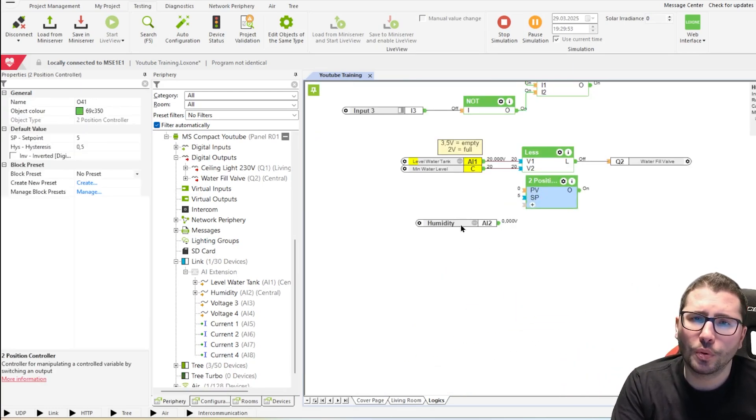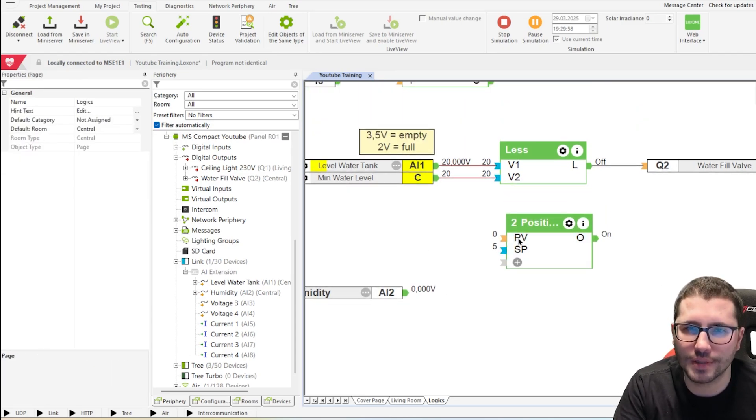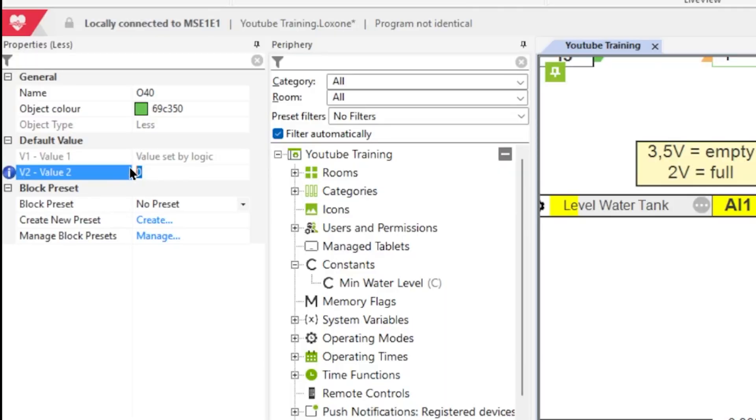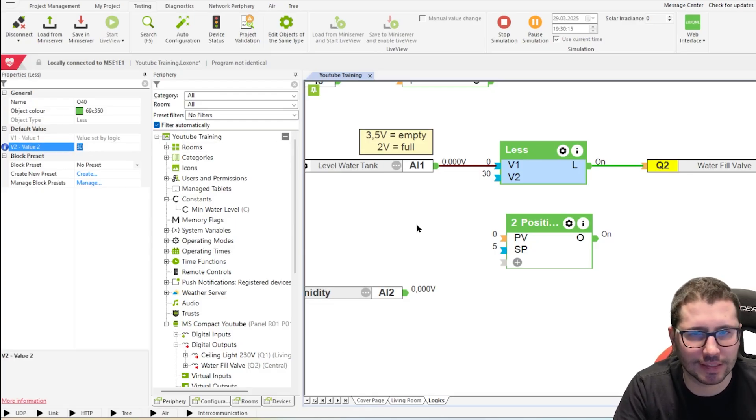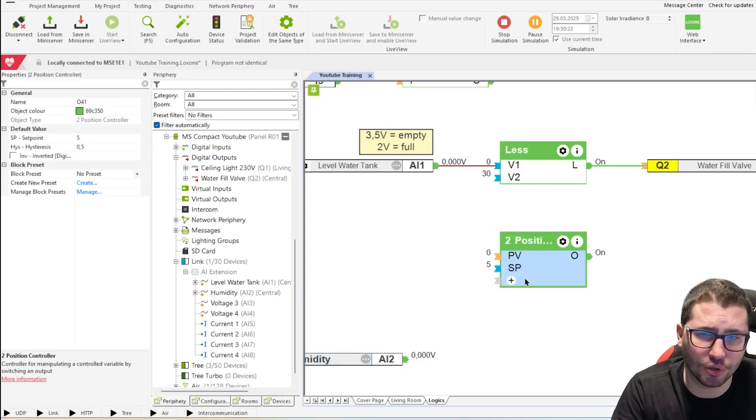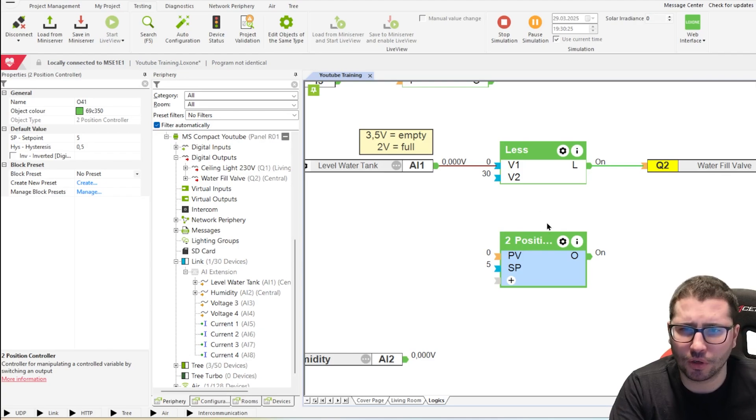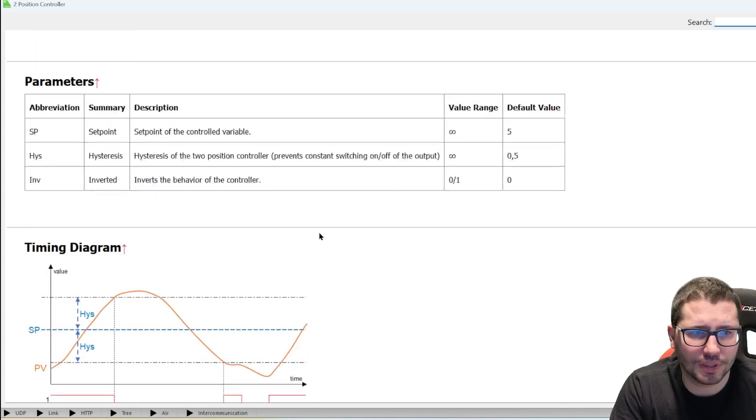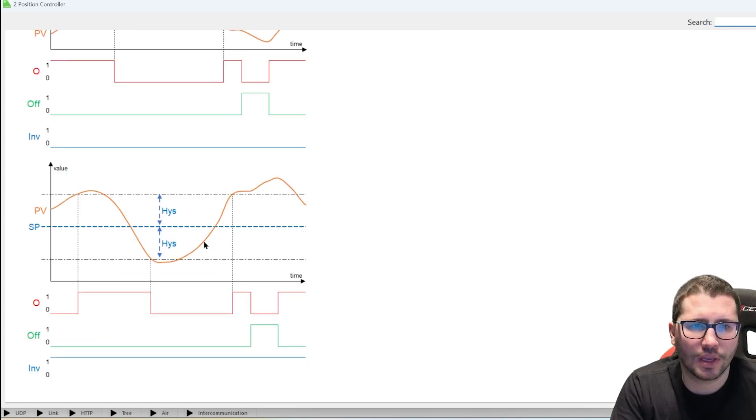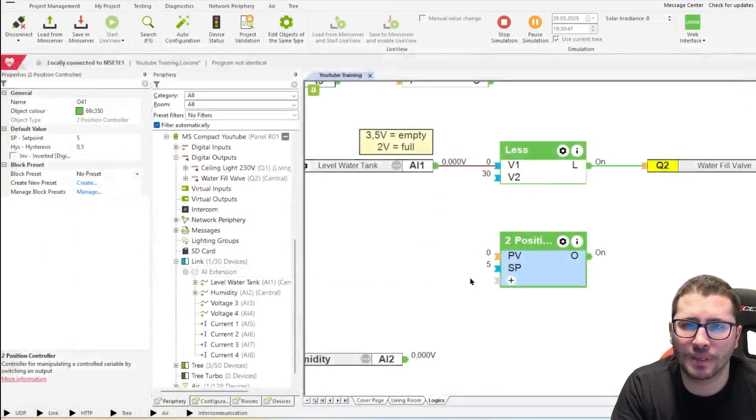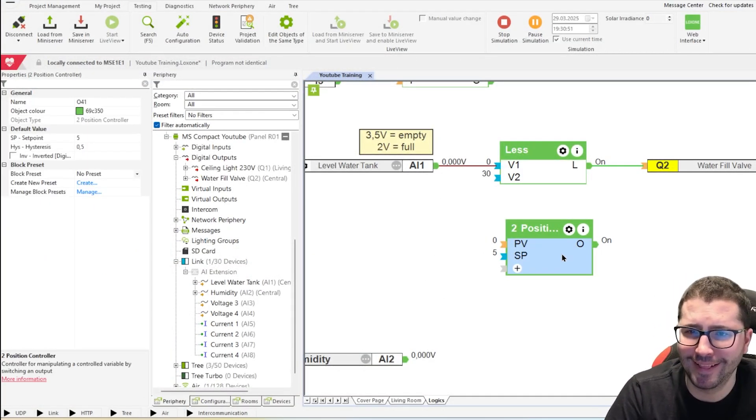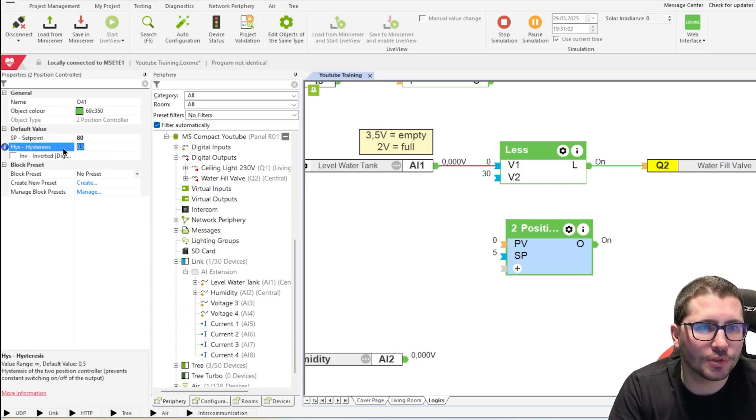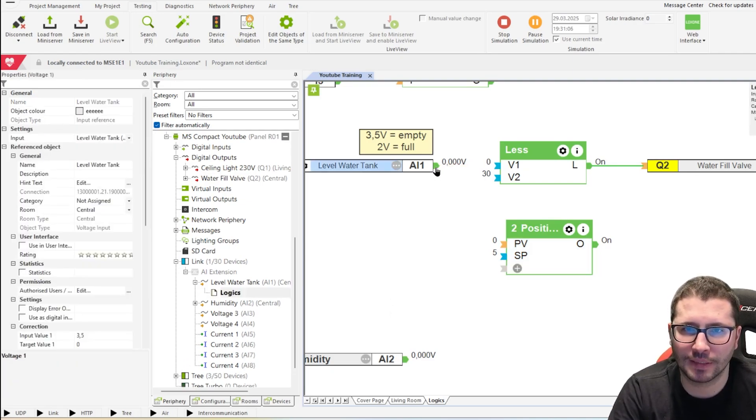That's where the two position control controller comes in hand. And before I show you this one, what I forgot is that we do not need the constants anymore. Because here in the less function block, we can set the value, let's say 30. So you see it without creating a constant. That's super fast. I love it. Now let's make this logic a little better. There is a two position controller. When you have no clue what this block does, any block, then you go into the info icon. Also offline, when you have no internet on the site, there is offline documentation as well. Then you see, okay, there is a set point and there is a hysteresis. You can read through this and you can understand maybe by the diagram. Let me explain it to you because otherwise it's assisted reading, which I don't like.